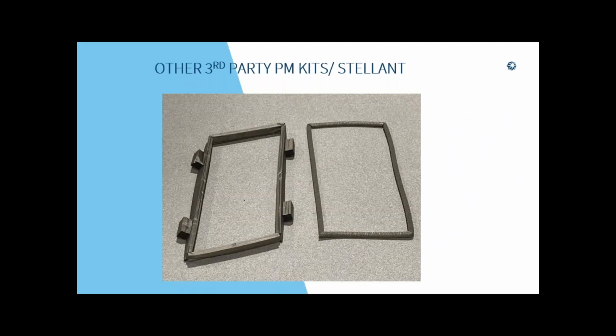This gasket right here is not the silver yarn. It is fabric over foam, but it's the wrong fabric. It's a metal weave. It does not absorb anything. The contrast and saline will just run right onto that and go right onto your CPU board. This gasket with the silver nylon is an open weave with foam under it to absorb that contrast and that saline. That's what it does. If contrast and saline gets in there, of course you have to replace it because it's no longer doing a gasket's job, especially with contrast. It becomes hard.